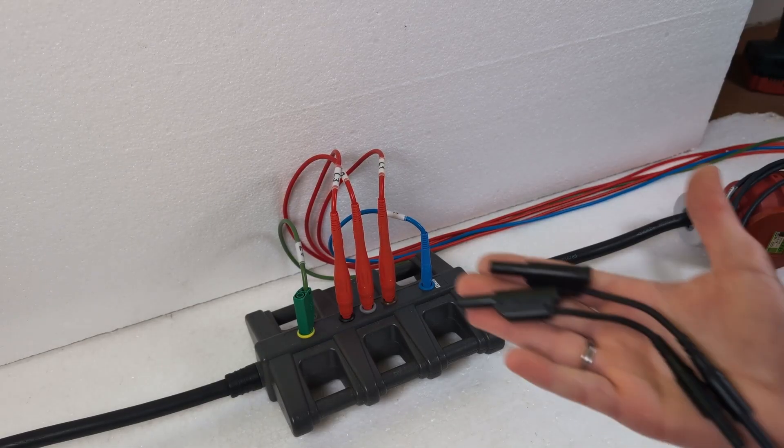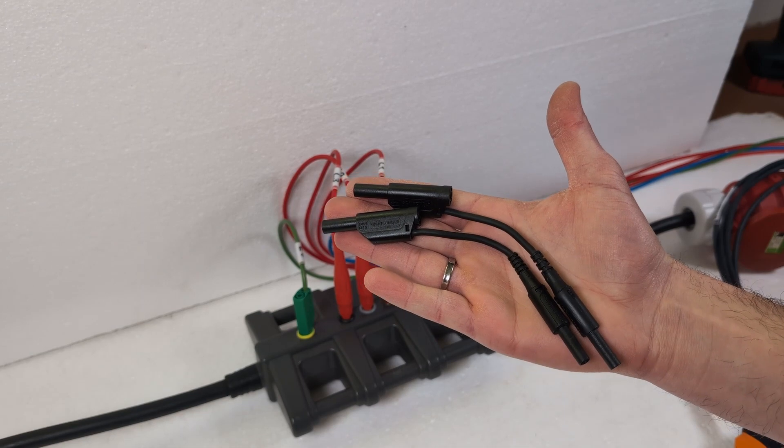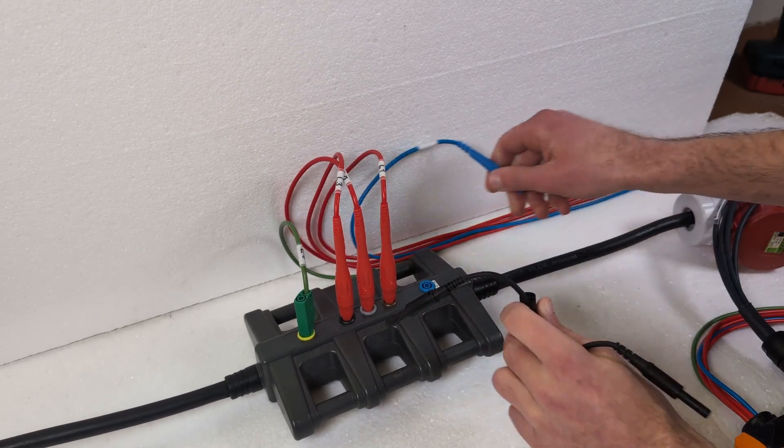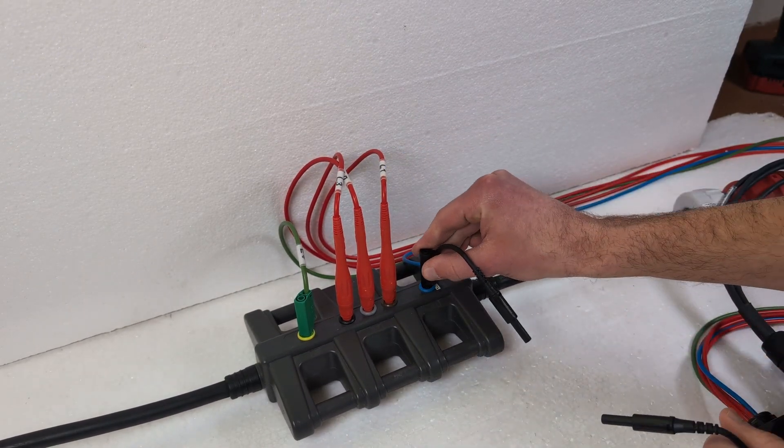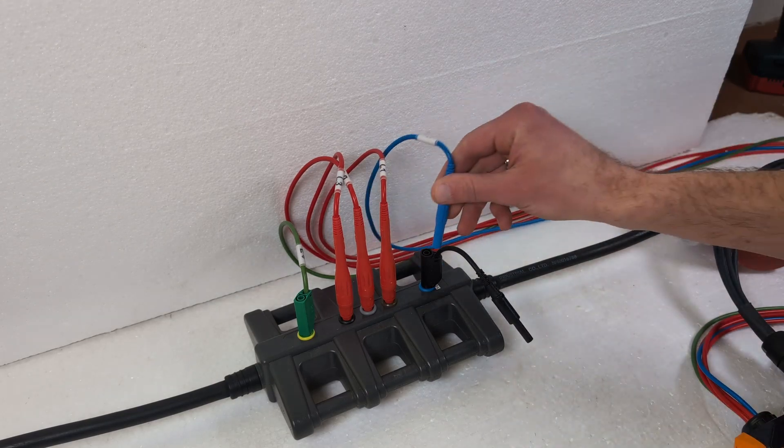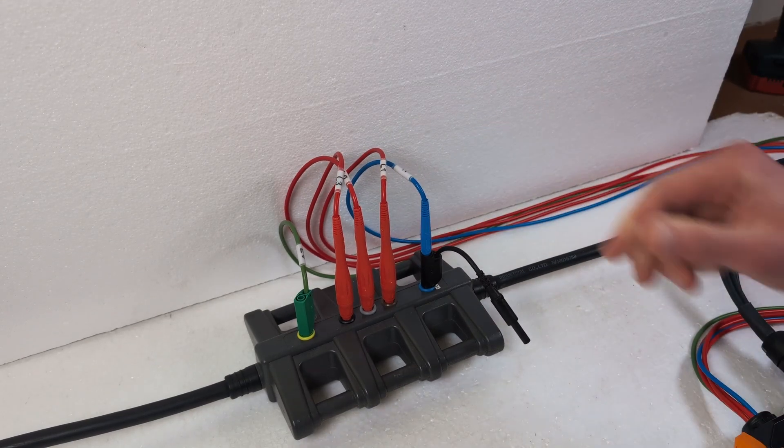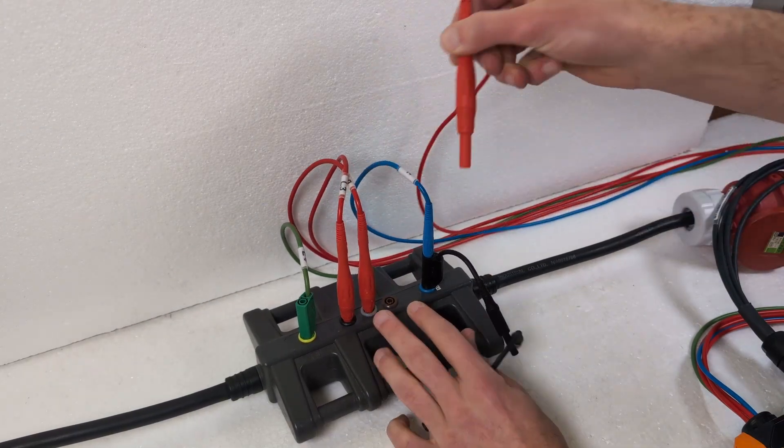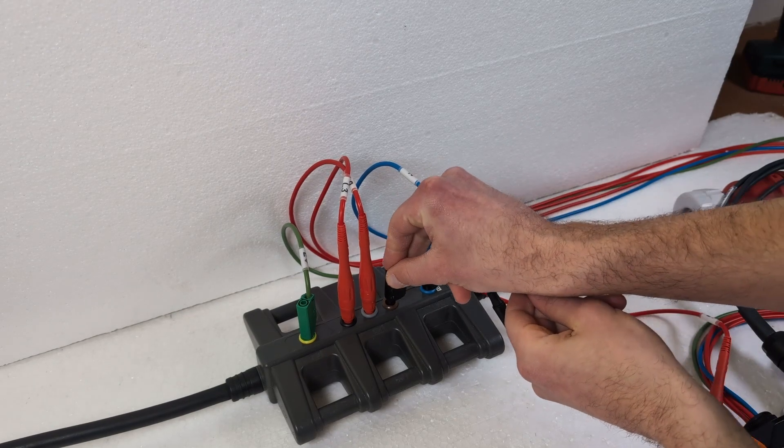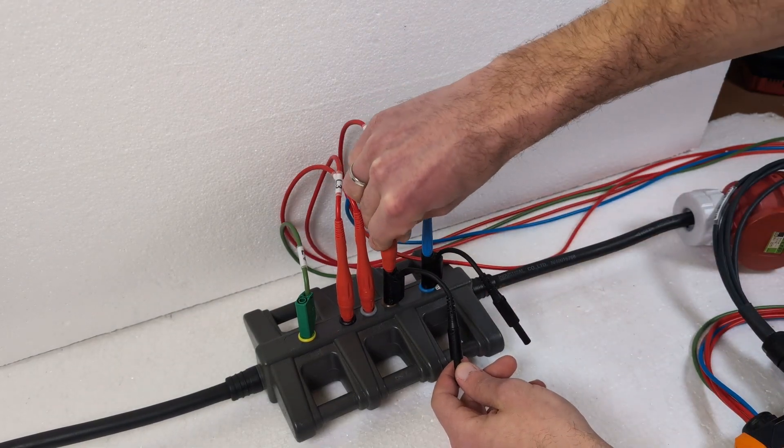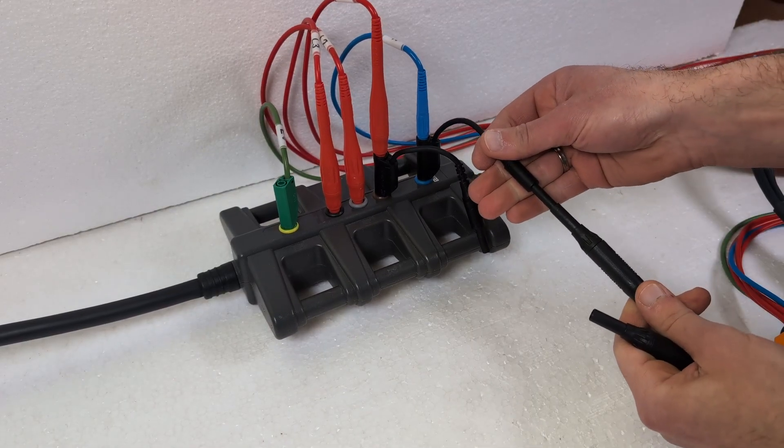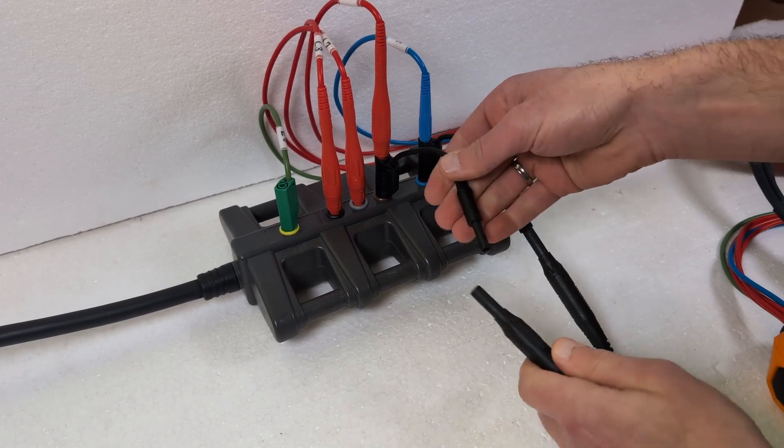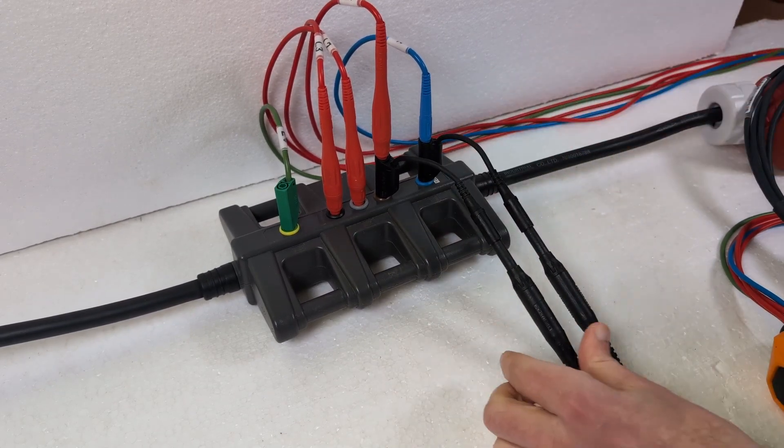Alternatively, I can also use the adapter cables to tap the voltage directly where I measure it. Simply connect between the phase conductor and the neutral conductor. Please note the voltage range of 100 to 400 volts AC or 100 to 300 volts DC.